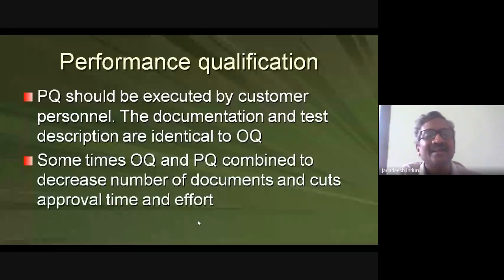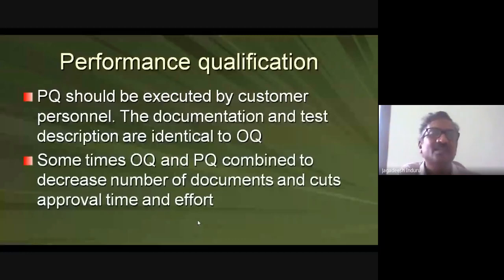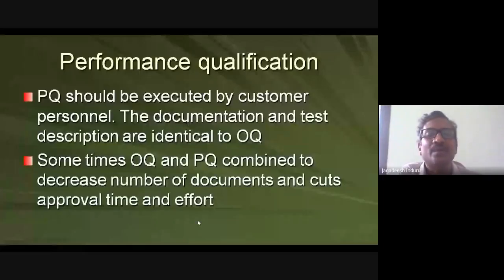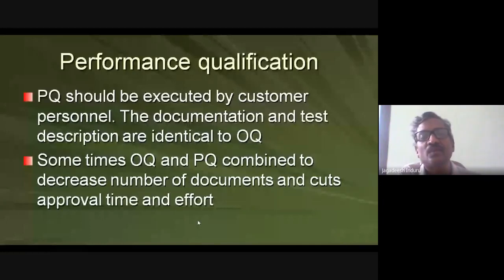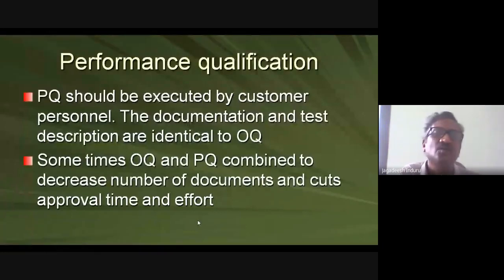PQ should be executed by the customer's own personnel — you learn, train, and operate the equipment according to your factory's requirements, such as desired hardness and friability for tablet punching. The documentation and test description in PQ are identical to OQ, but now you work at your specific operating point. For example, if the dryer works up to 250°C in OQ but your actual drying temperature is 150°C, you hold it at 150°C for two hours and verify it is stably maintained.